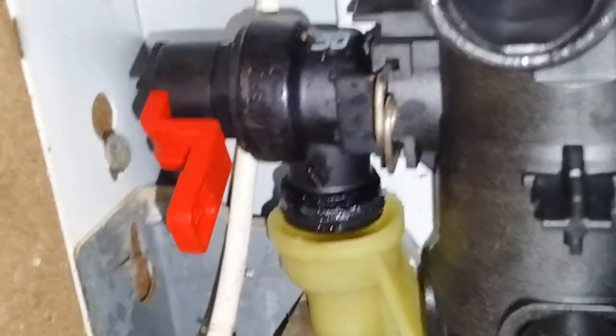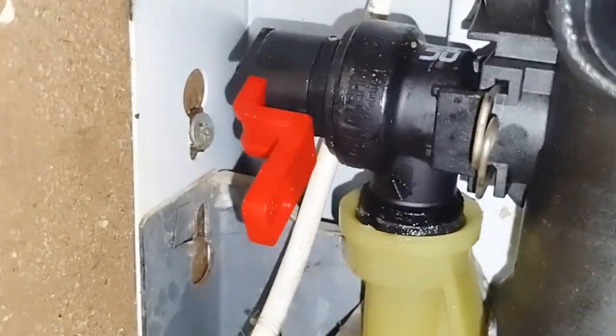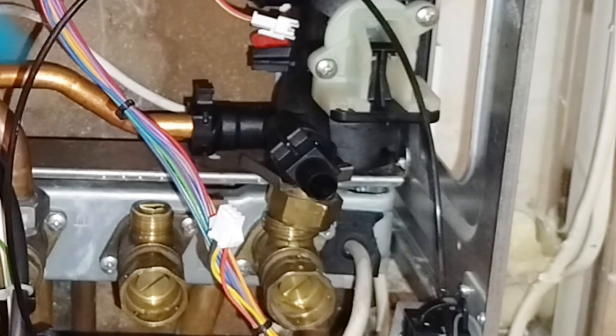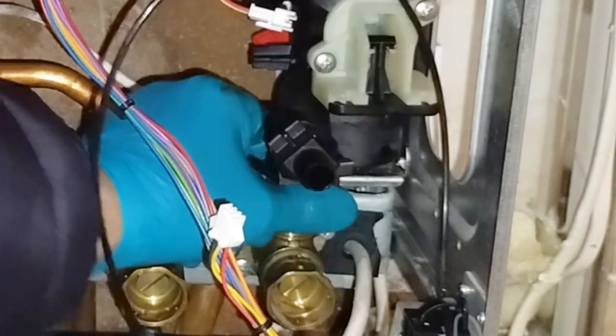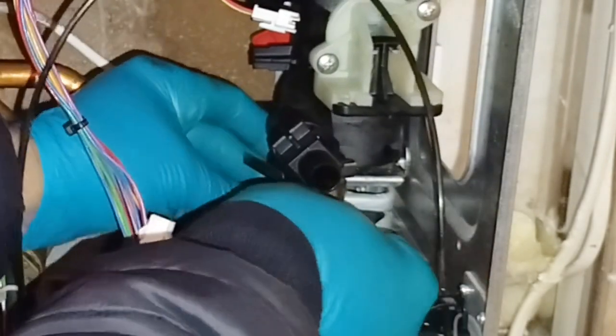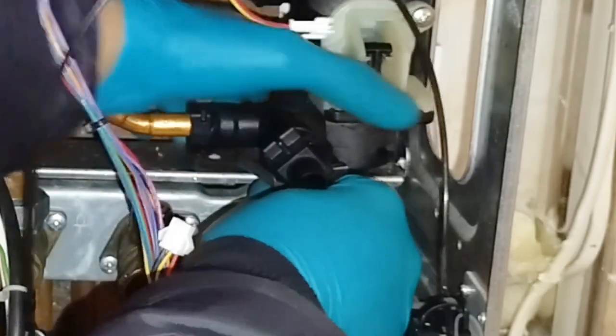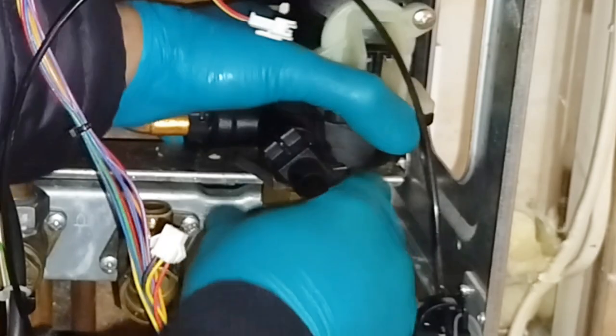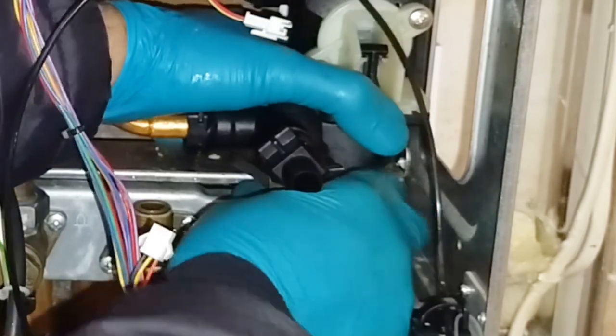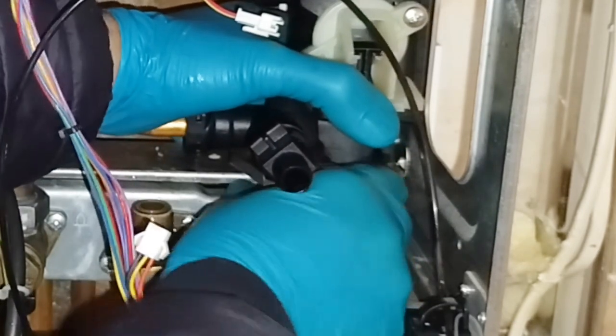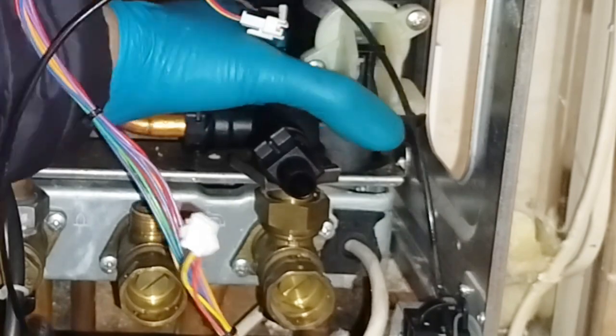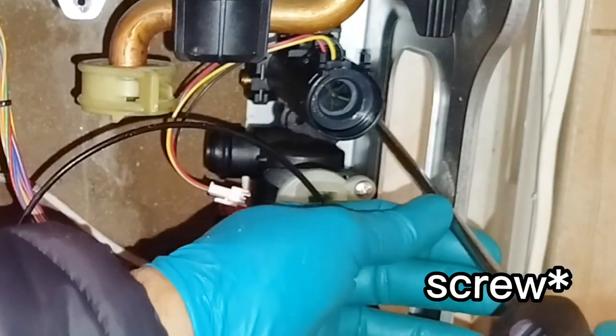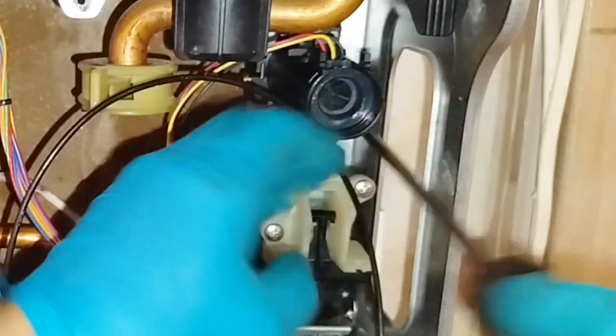All right, so this is the back of the whole manifold. We've tapped it from underneath in order to push the assembly which we took off. So now we are going to renew always. I would always renew the fiber seals, any seals, especially the fiber seals which sit on these connections, because you can take a risk, but if it leaks while you're trying to finish it, it will be a pain to replace it then. All right, so now we've tightened the nut which will hold the return assembly onto the body of the boiler.